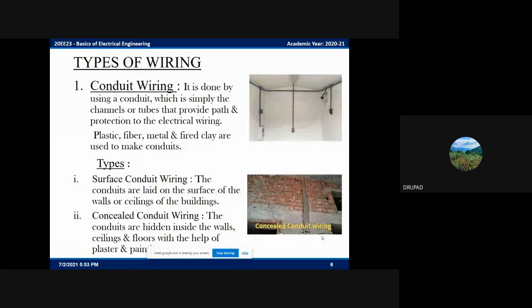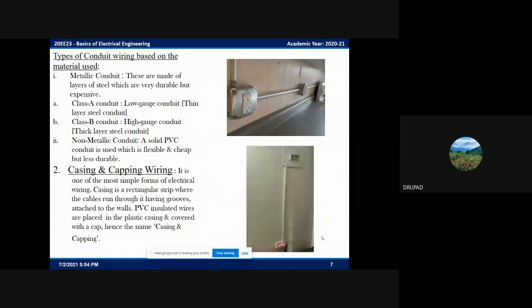And the type of wiring is conduit wiring. In conduit wiring, there are two types: surface conduit wiring and concealed conduit wiring. Surface conduit wiring is what you can see on the ceiling, and concealed conduit wiring is built into the bricks. There are types of conduit wiring based on materials, such as class A, class B and non-metallic conduit. Another type of wiring is casing and capping wiring.